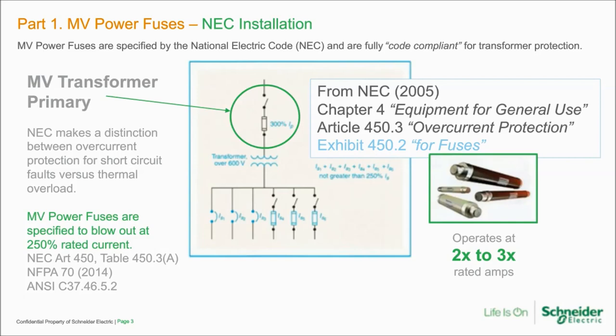The NEC chapter for medium voltage is actually in the chapter for general equipment — article 450.3 for overcurrent protection. NEC makes a distinction between the two types of overcurrent: short circuit versus thermal overload. Thermal overload is like Clark Griswold's Christmas lights scenario, while short circuits involve things like lightning strikes. MV fuses are specified by NEC to be fully compliant for transformer applications. The thing to note is that power fuses blow between 250 and 300 percent of their rated current — this is how they work physically and how the code intends them to be applied.